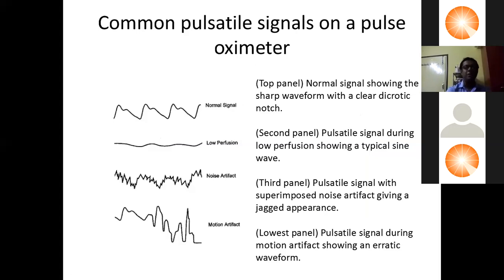And this is the normal plethysmograph. When you are recording SpO2 on a monitor, it is very important to have a normal plethysmograph, because if you don't have it, the number showing on the monitor may not be correct at all. In the second picture you can see the perfusion of the patient is very low, so the curves are flattened. In this situation, the accuracy of the SpO2 is lower.